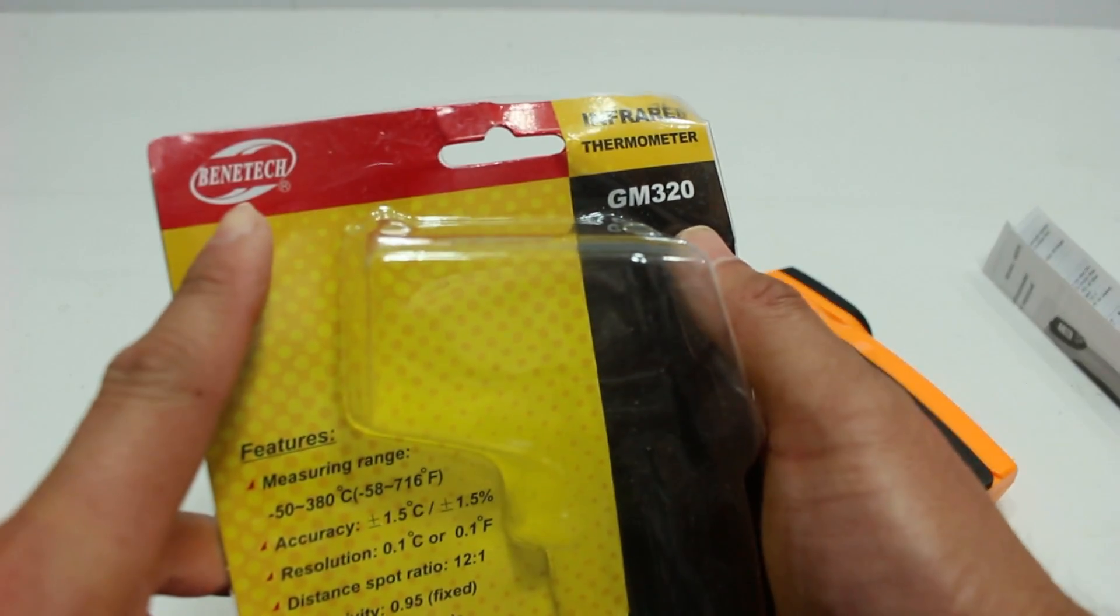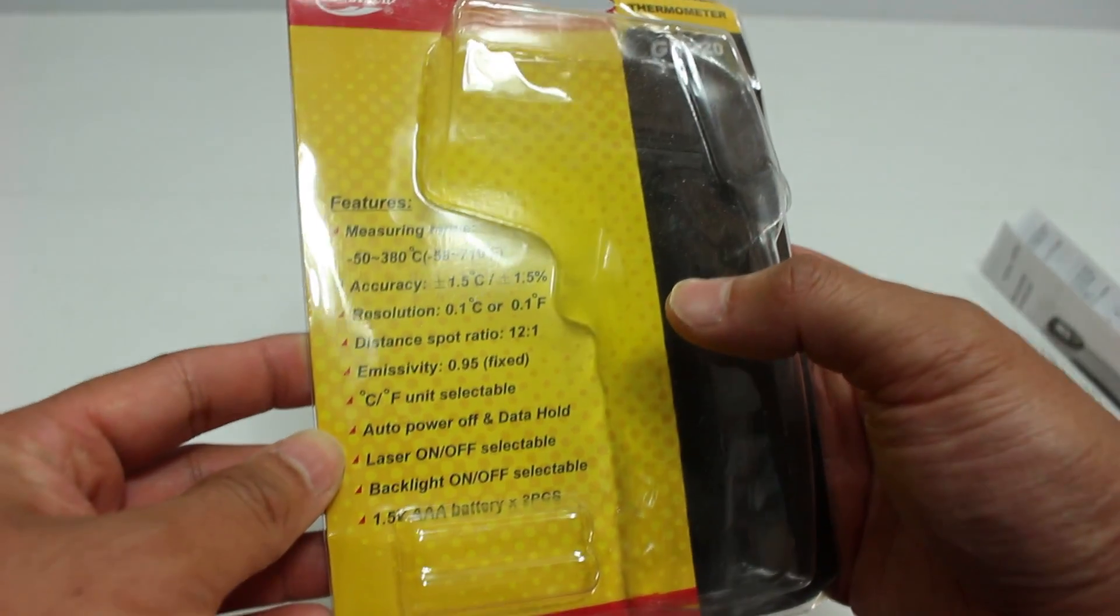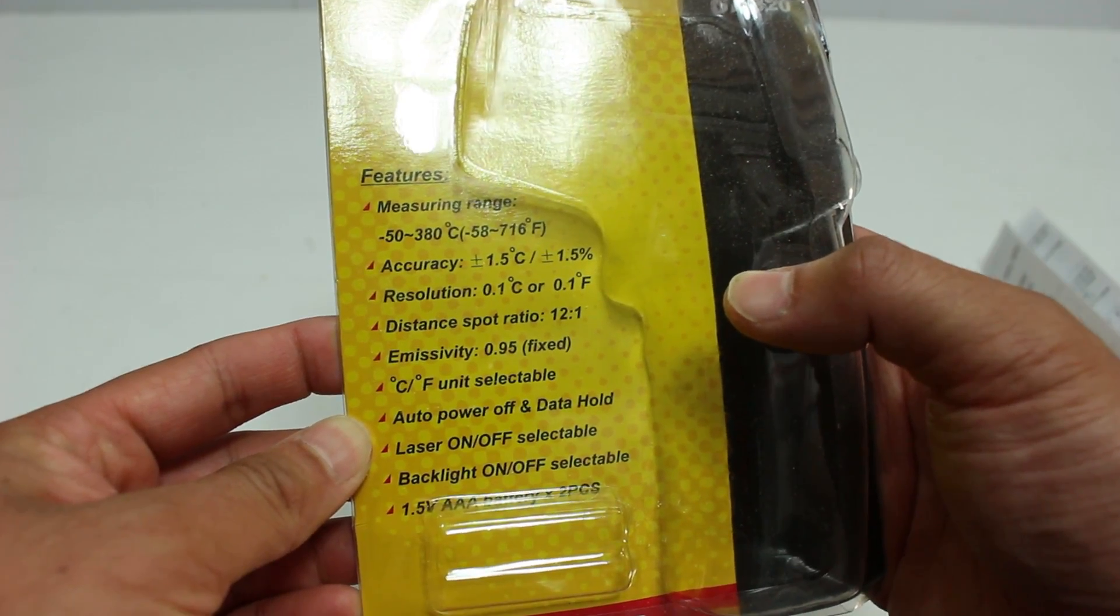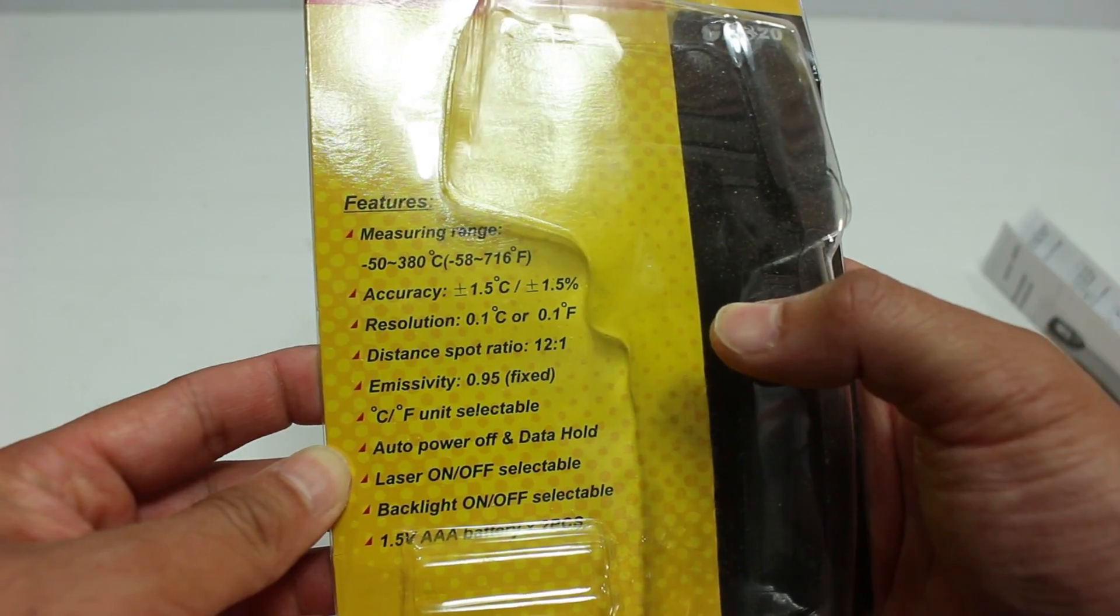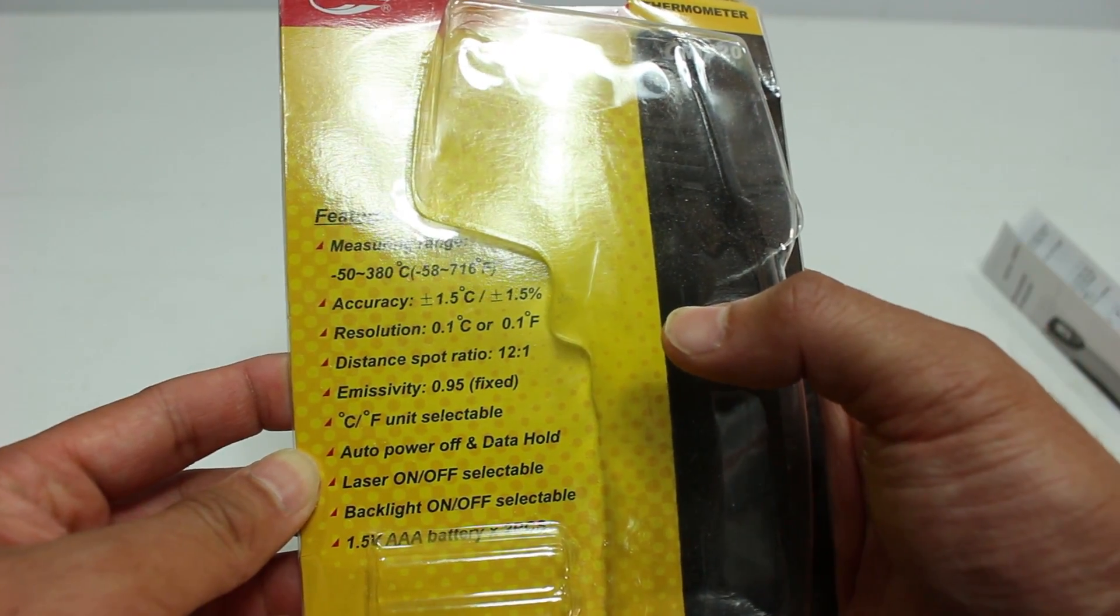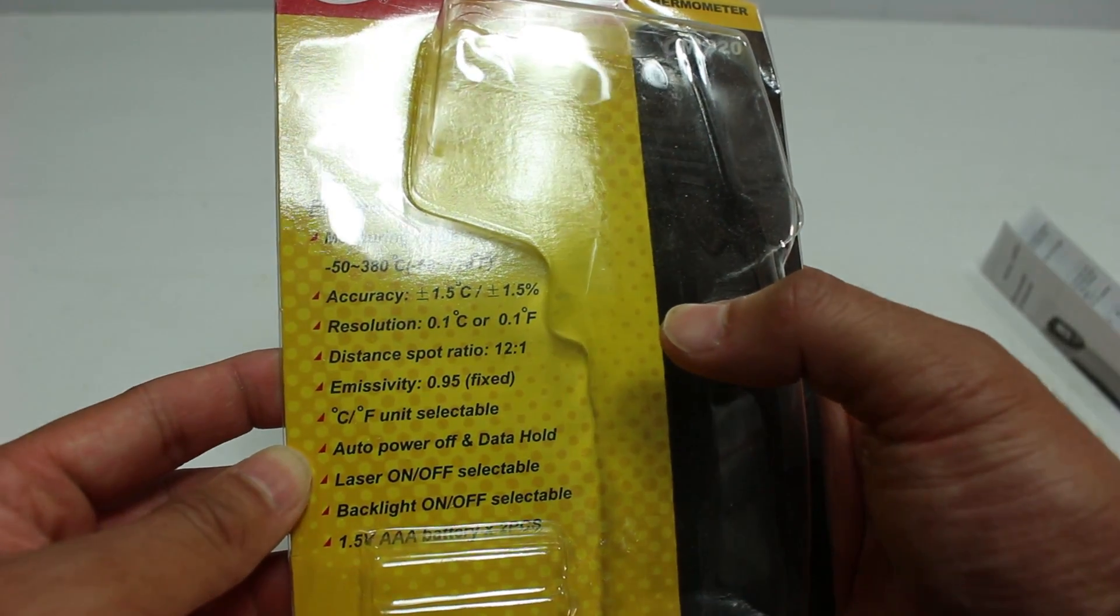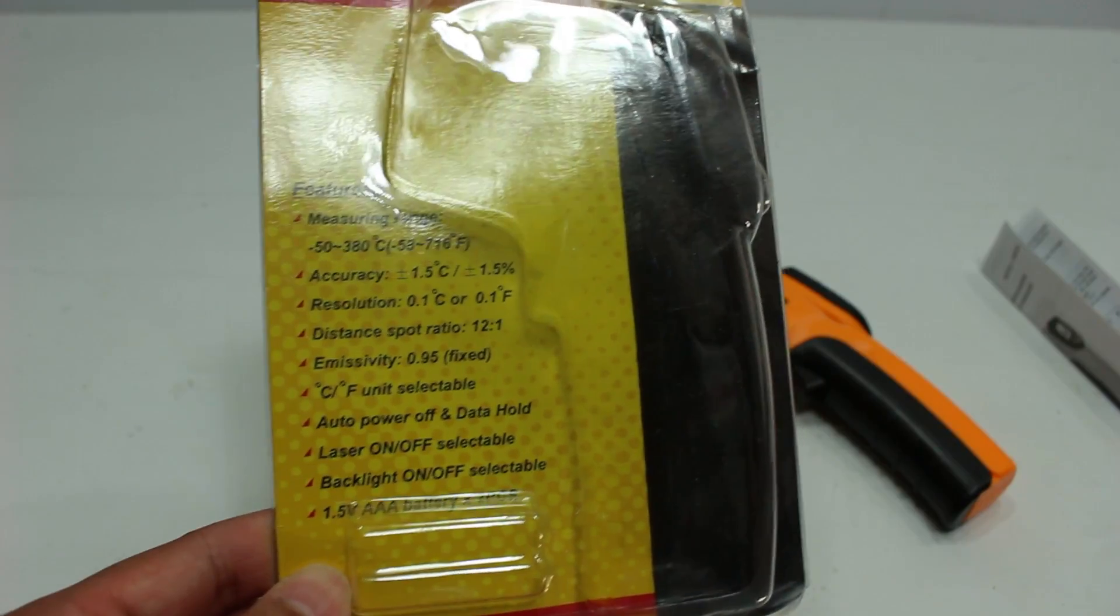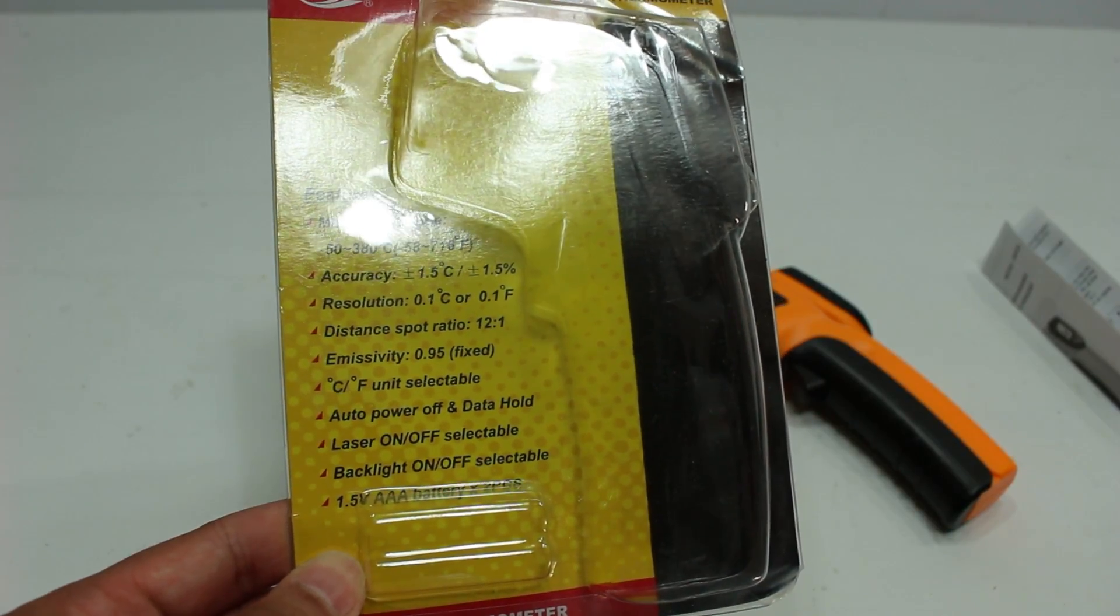It's a Benetech. So what are the features? It's good from minus 50 to 380 degrees Celsius, or minus 58 to 716 Fahrenheit. The accuracy is plus or minus 1.5 degrees Celsius or 1.5 percent, a resolution of 0.1, a distance spot ratio of 12 to 1, and an emissivity of 0.95 fixed.